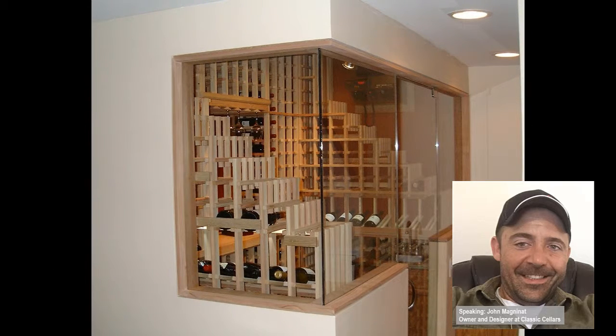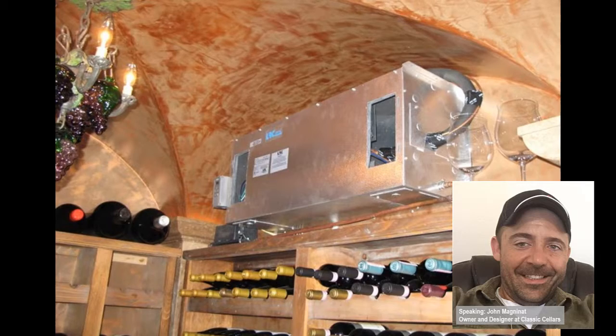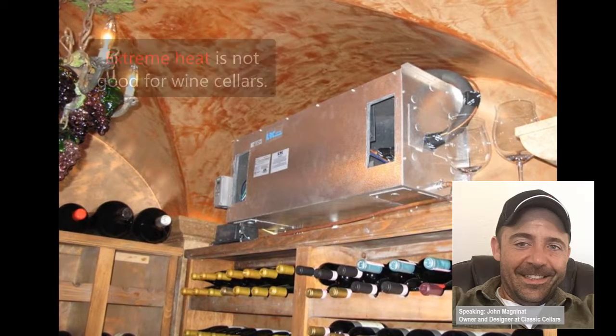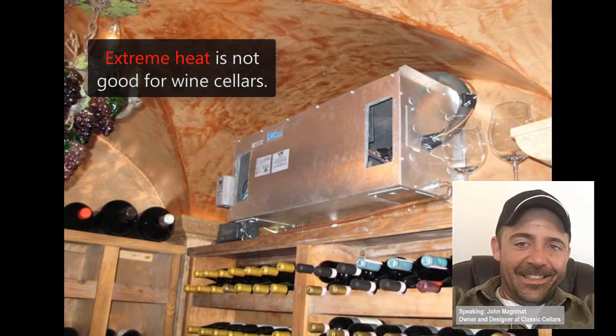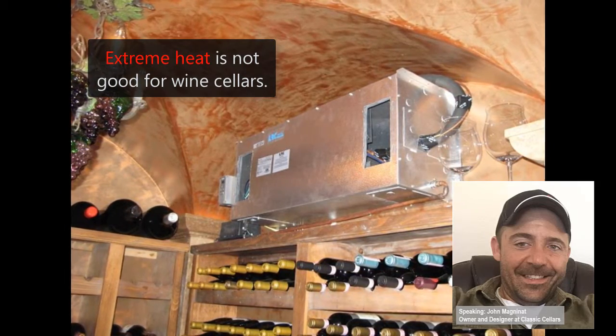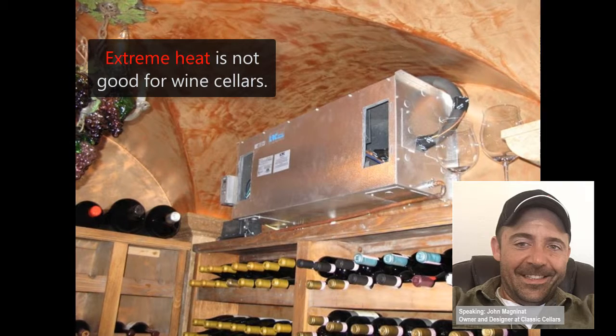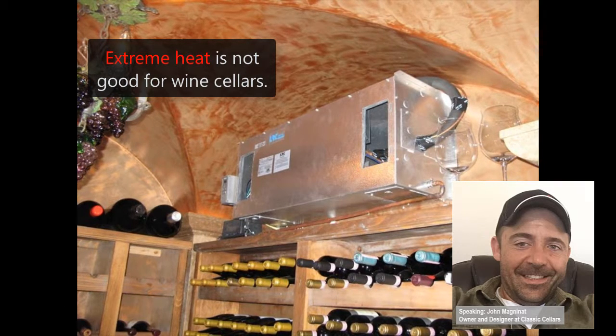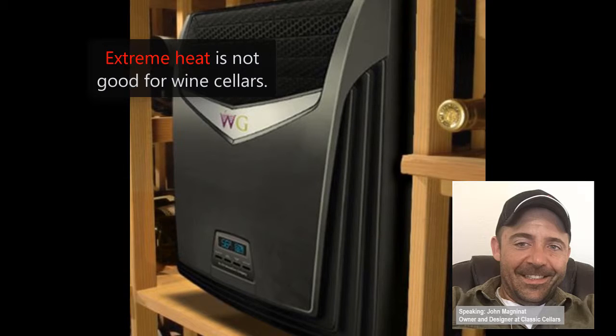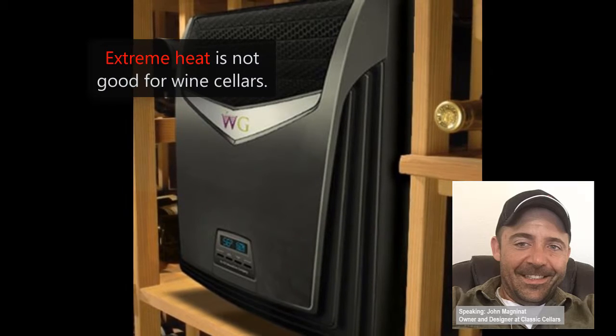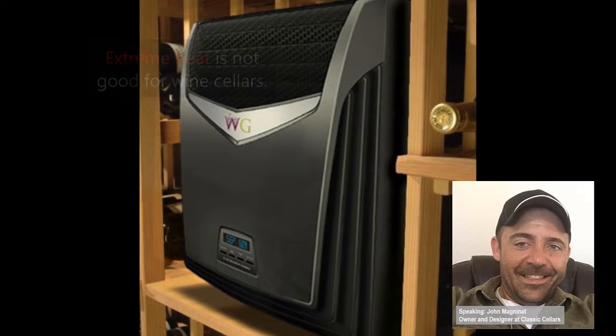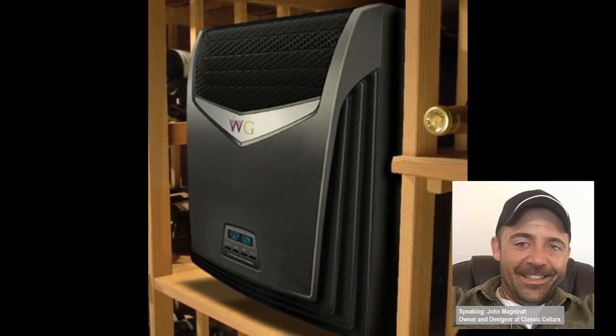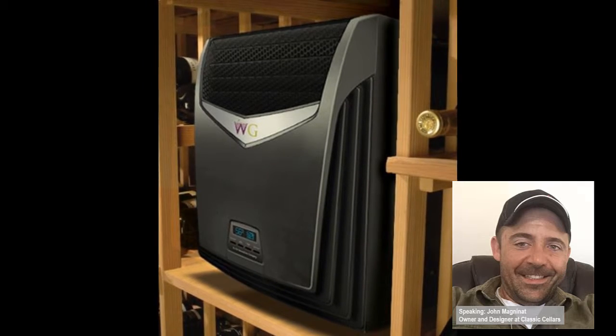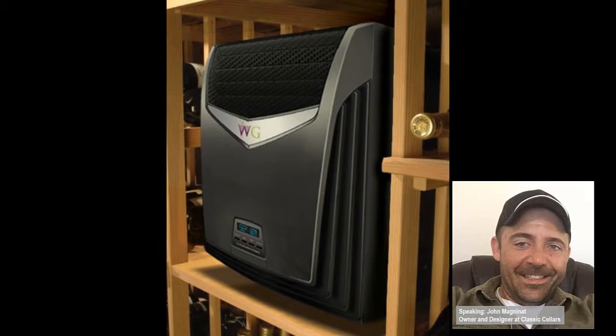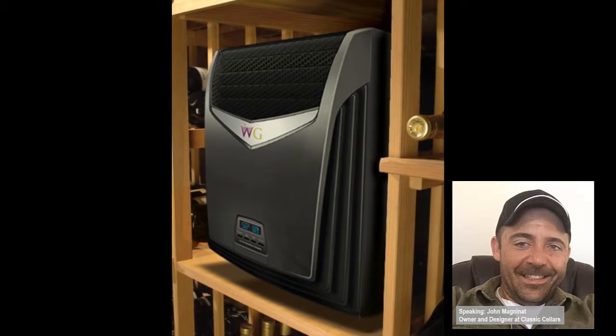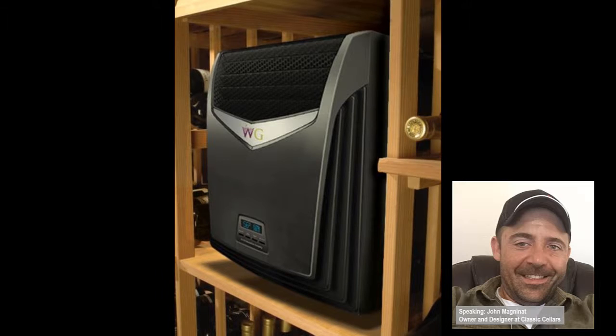And then the heat. There's times where it gets 105, 108 degrees here, and the air conditioners just can't keep up, and it's real hard on the equipment. That's another issue to look at. Some of these self-contained units need to have high ambient kits on them so they can run in temperatures over 100 degrees. And where you're getting your condenser air from is real important on a self-contained unit. You get guys that take it right off of the roof deck, and that air is 160 degrees. Well, it'll kill that machine. It's not going to function right, and you're going to end up seeing machine failures because they're just not made for that kind of temperature.